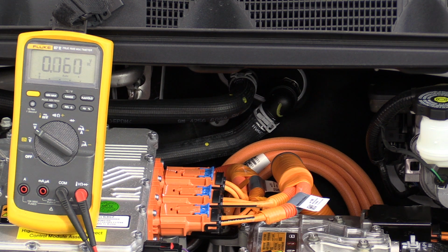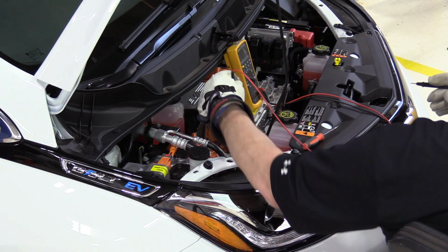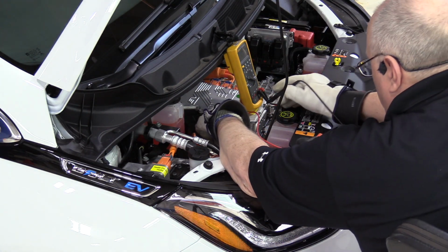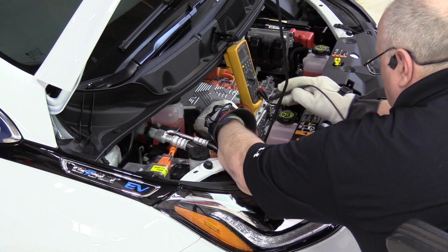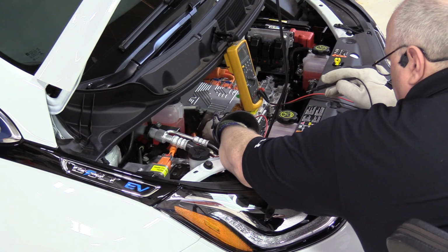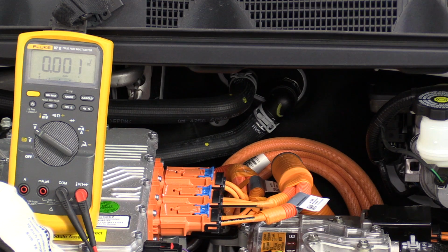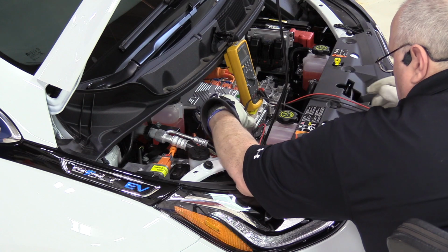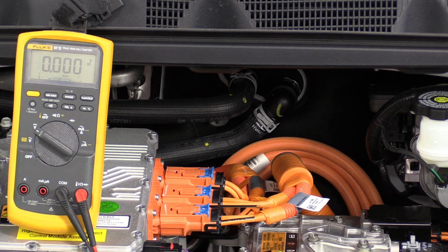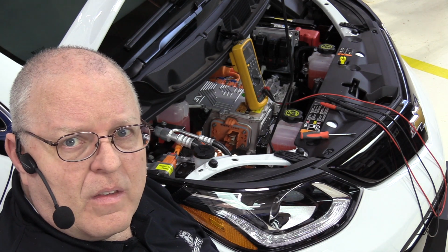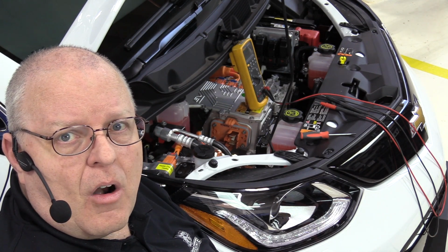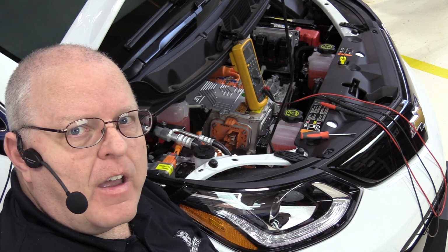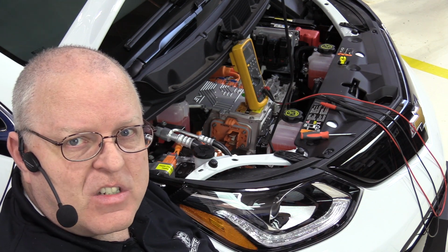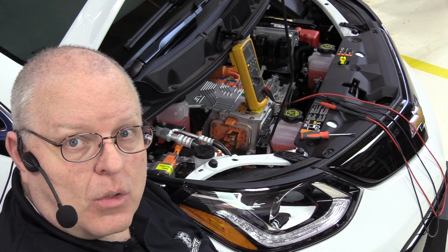So we have no volts, and so then we're supposed to check the same thing on the electrical connector that we disconnected. So now we go from one terminal to ground, we have no voltage. The other terminal to ground, no voltage. And then the 2 terminals to each other, no voltage. Okay, that tells us that the contactors in the battery are most likely open, but we will verify it one more time down at the battery when we disconnect that electrical connector. So let's go do that next.